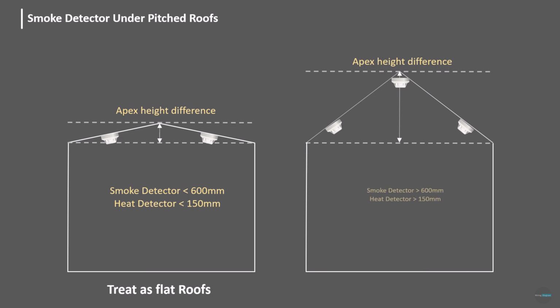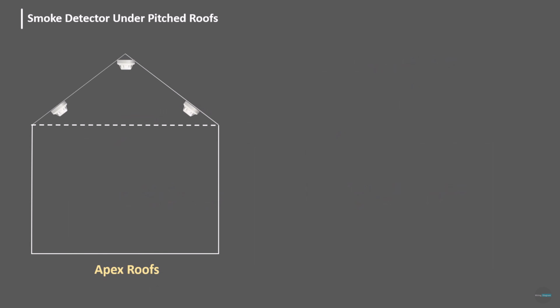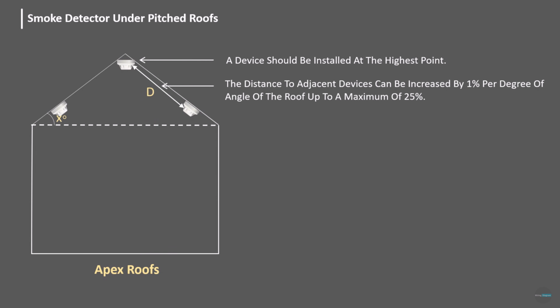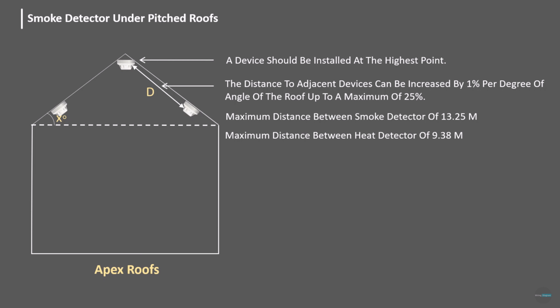If the apex height is more than 600 millimeters for smoke detectors, more than 150 millimeters for heat detectors, then the roof is treated as an apex roof. Detector installation in apex roof as below. 1. The first device is installed at the highest point of the roof. 2. The distance for the second device is increased by 1% per degree of roof angle, with a maximum increase of 25%. This results in smoke detector maximum distance of 13.25 meters and heat detector maximum distance of 9.38 meters.